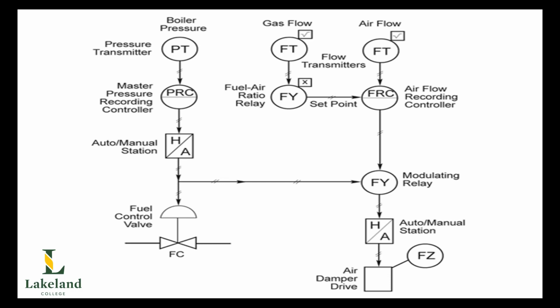Because in this control philosophy the fuel control valve is being signaled first, then the damper drive, fuel flow is the leader. In reality, don't forget, this is all happening simultaneously. We're just talking about from a control or an algorithmic perspective that the fuel flow sets the airflow. On the right hand side, we've got our two flow transmitters of what we're actually monitoring now, and that is our airflow and our gas flow, or fuel flow if you like. Hence the name of this system, fuel flow airflow.